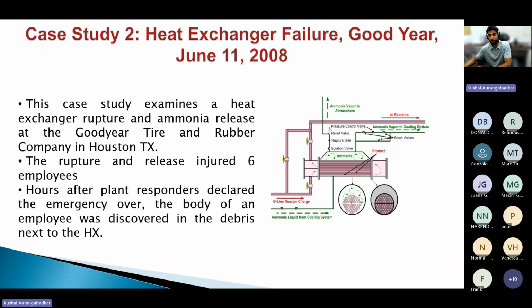On the morning of June 11th, an operator needed to clean this piping with steam as a CIP, so he closed the block valve, isolating the ammonia pressure control valve from the heat exchanger. And basically, steam flowed through the heat exchanger, heating the ammonia, boiling the ammonia, causing the pressure in the heat exchanger to rise. The closed isolation valve and closed block valve prevented the high pressure ammonia from escaping, and pretty much it ruptured the disc and the shell of the heat exchanger. It injured 6 employees and killed 1 person.